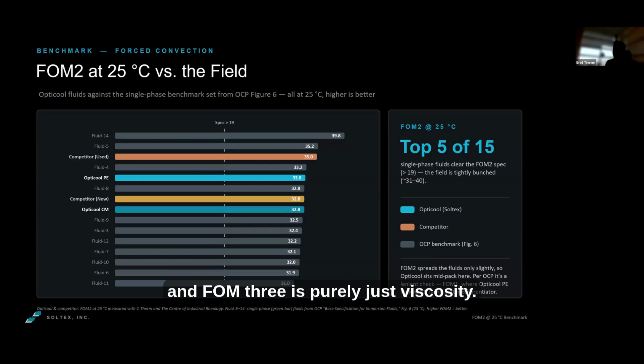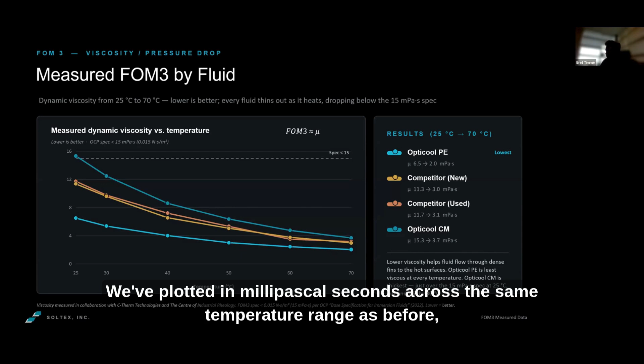The first thing to make note of is for FOM3, lower is better. A thinner fluid flows more easily through the dense fins of a heat sink and reaches the hot surfaces more efficiently, so it ends up cooling better. We've plotted this in millipascal seconds across the same temperature range as before, and you can see the dashed line shows the spec at 15, for 25 degrees Celsius.